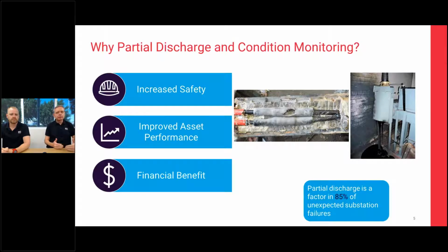And due to the proportion of cables affecting the network performance in the SAIDI, when you look at the study, what the statistics generally show is that if you can proactively replace a failing cable or a failing joint, rather than waiting for it to fail, you will typically save around 30% of the cost, or 33%, a third of the cost of letting it fail and fixing it.